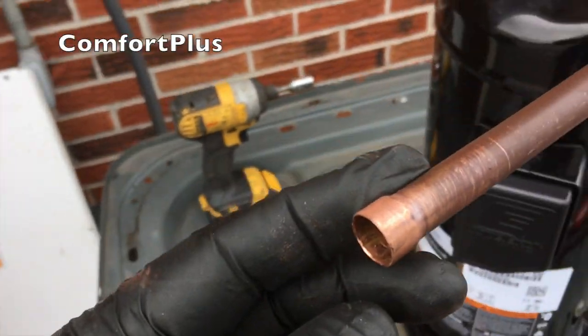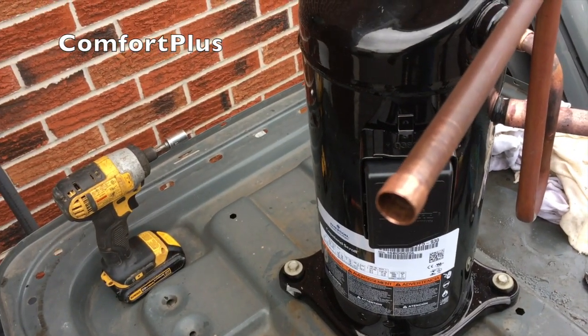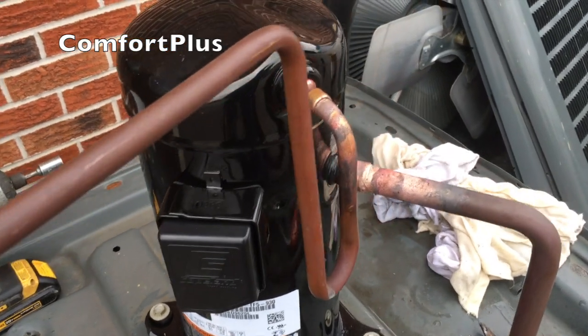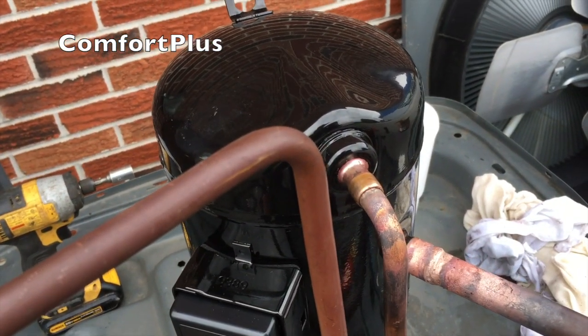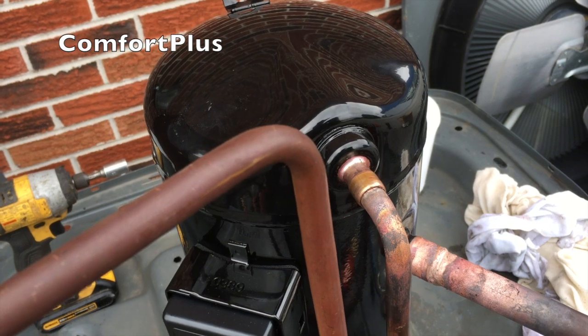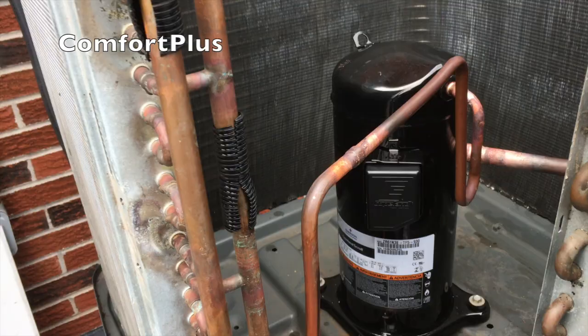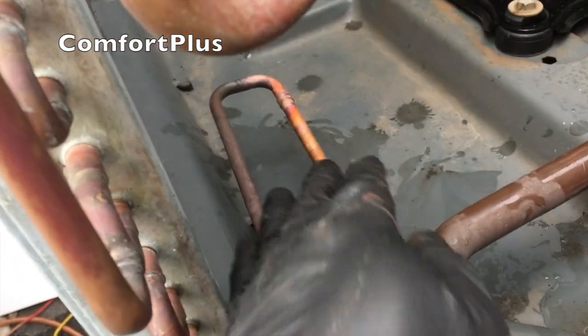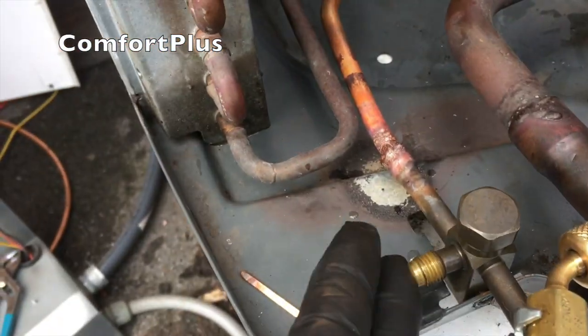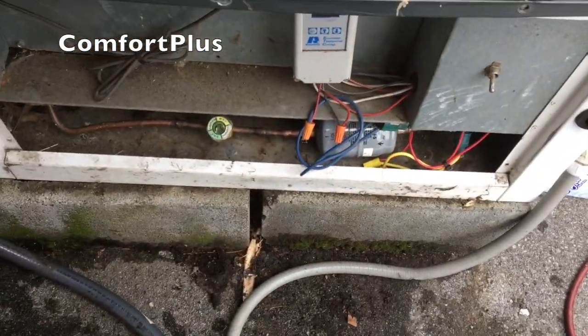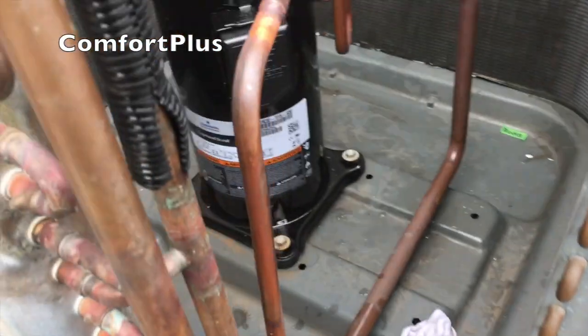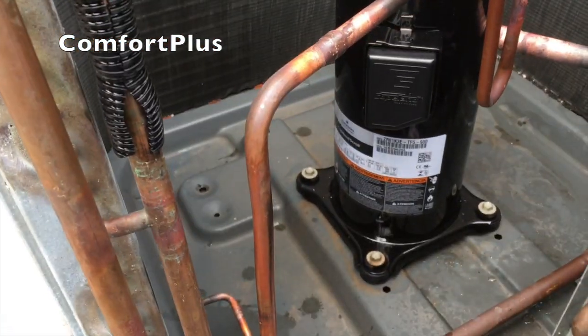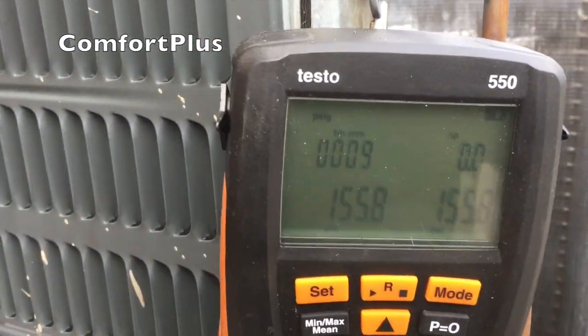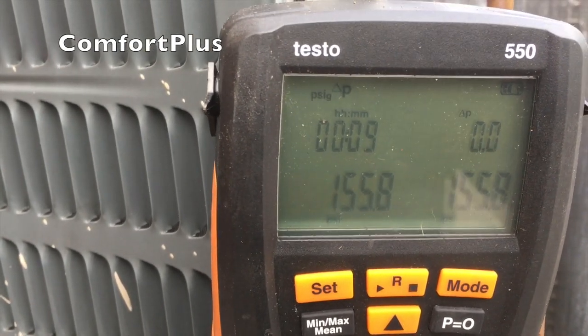I've already swedged it up here so I can put it back together when I set the coil back up on top. So I'll get this last connection inside brazed up, and then I'll be setting the coil back on it. So that was the last 2 connections. Still got nitrogen flowing. Got the new dryer down there. So we're going to pressure test, and if she holds, we'll pull a vacuum. It looks like the pressure test is going to hold. We've got 9 minutes, and it hadn't changed.